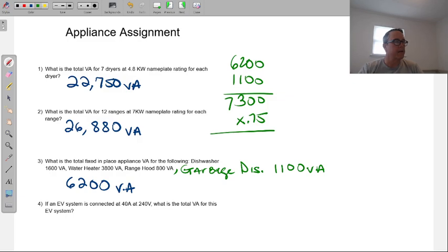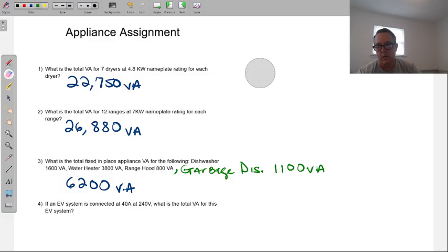You can't apply the 75% unless you meet both of those requirements: 4 or more, and 500 VA each minimum. But we don't have that in this one.